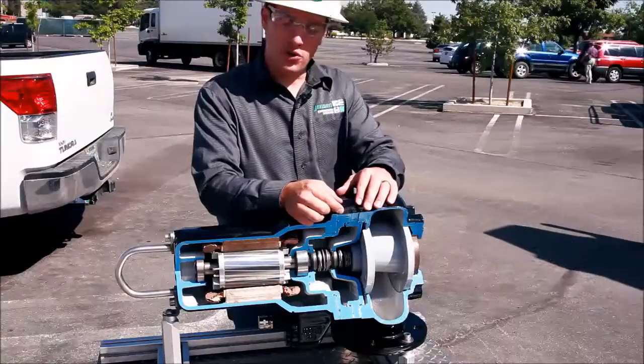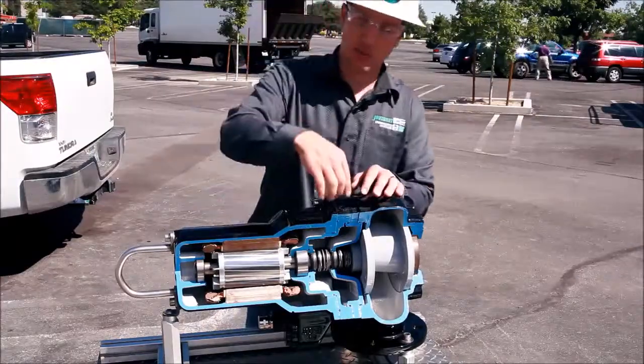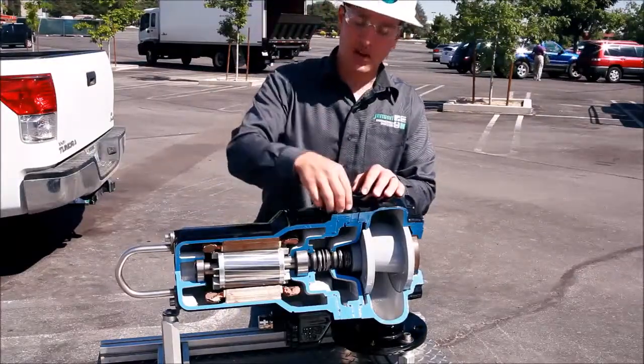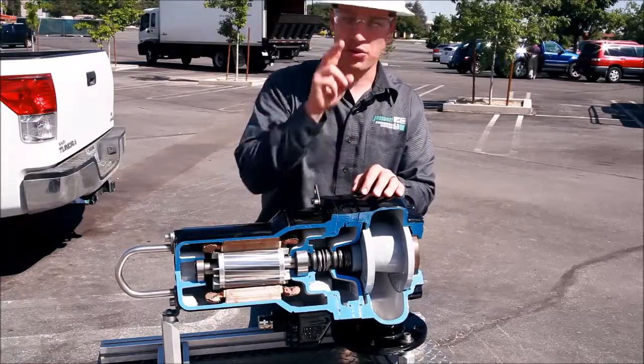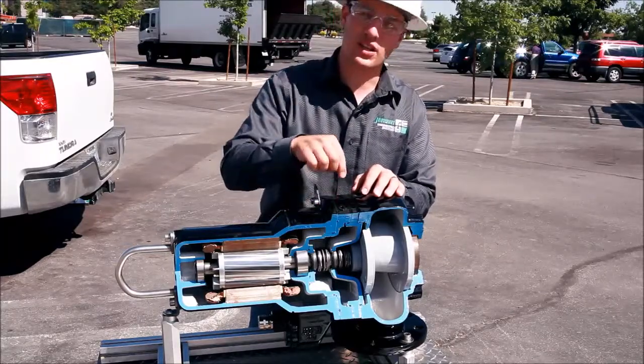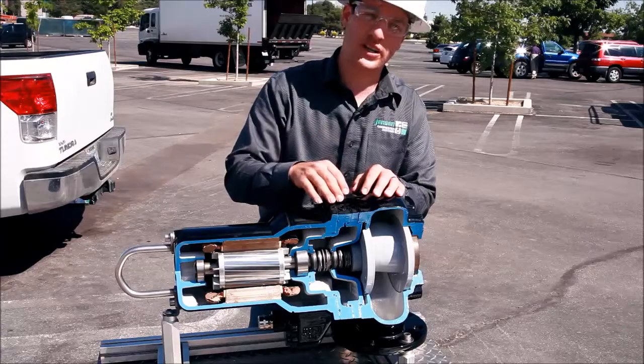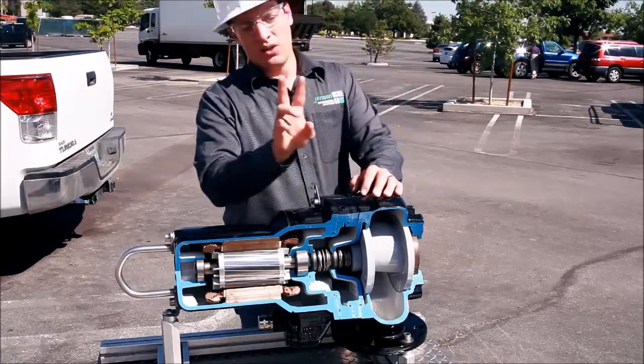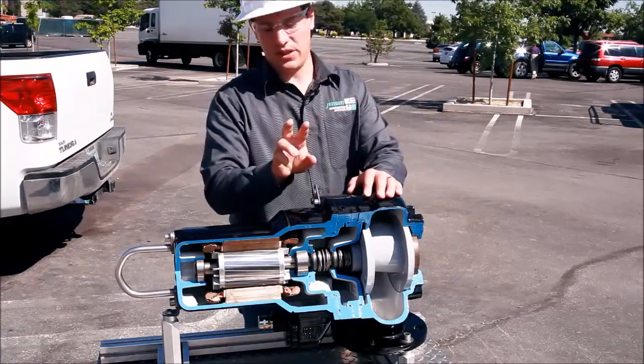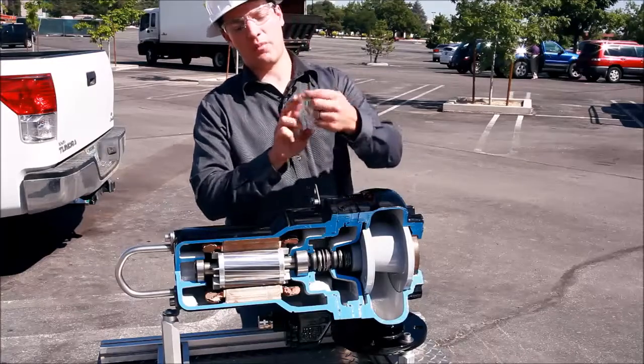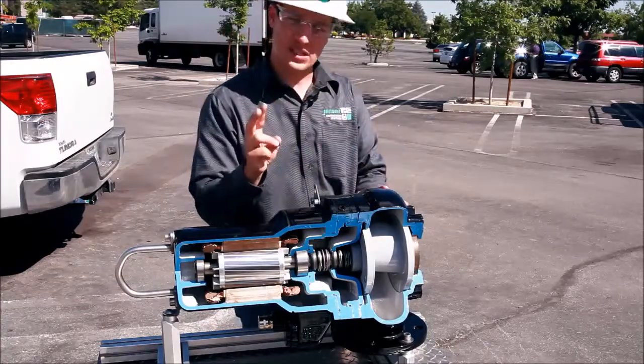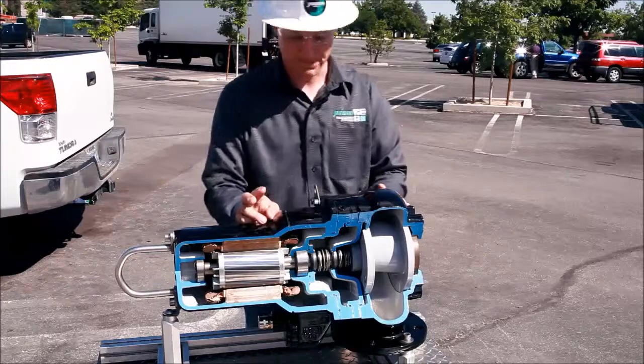If I was to remove the hex head, I could put my white mineral oil in there. And then what I leave in there is a two-prong wire that's inducing a low voltage current into the oil. The prongs are separated by a minimal distance, and the current is jumping from the prong, and there's a predicted resistance in the white mineral oil between the two prongs.